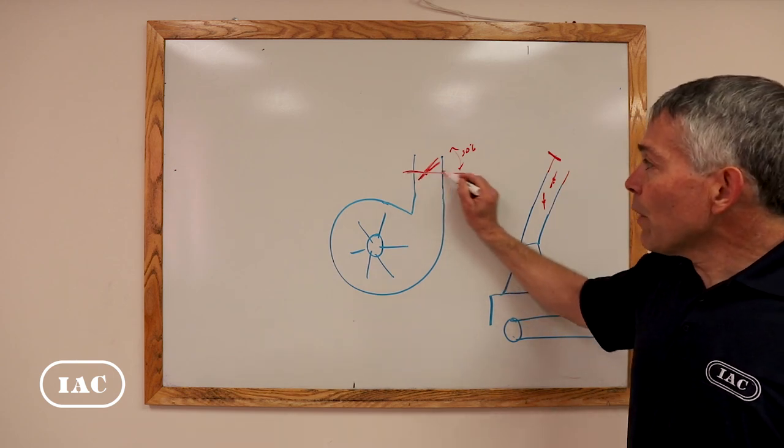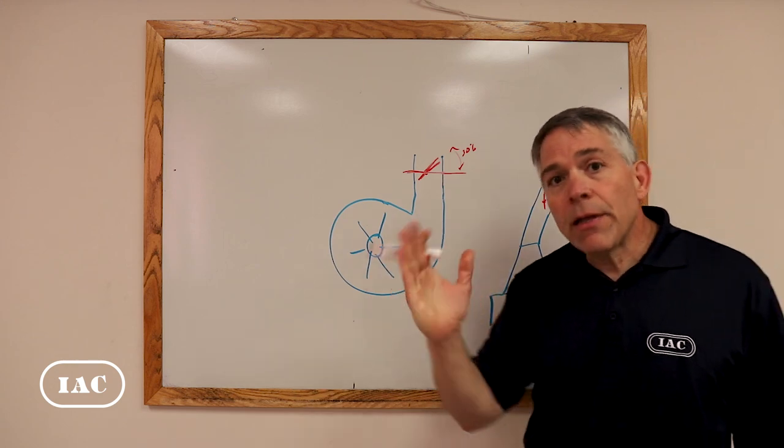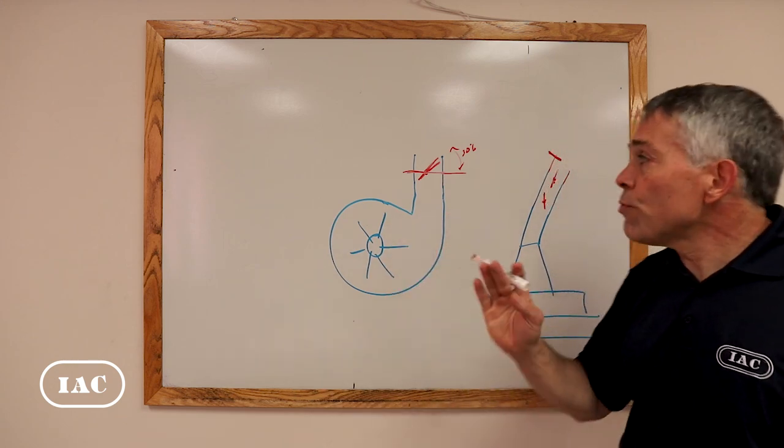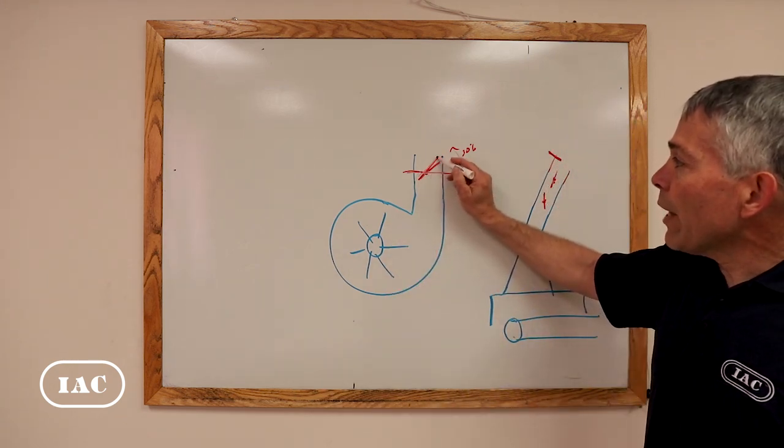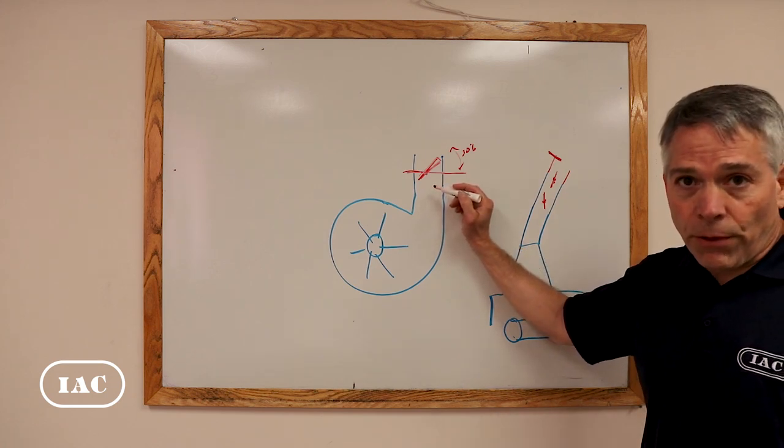So, be careful about your butterfly dampers. Play with it to get the adjustment that you need and don't just assume that because you've got a lever that shows 30% that you're getting 30% of the flow.